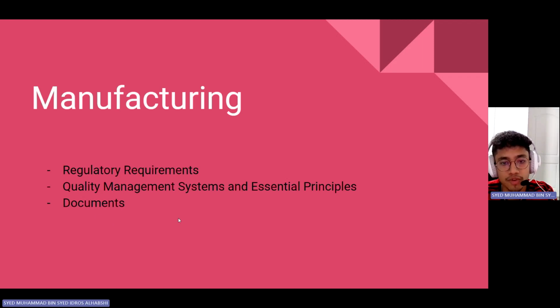Now, on to the good manufacturing practices. For regulatory requirements, standards and regulations were adhered to. Standards such as the International Organization for Standardization, also known as ISO, and the International Electrotechnical Commission, or IEC, that apply to the infusion pump were all met and adhered to ensure the safety of the patients and users when using the infusion pump. The quality management system and essential principles must be met by the infusion pump. For those criteria that apply to the medical device, they are met before being put onto the market in order to ensure the safety and well-being of users.